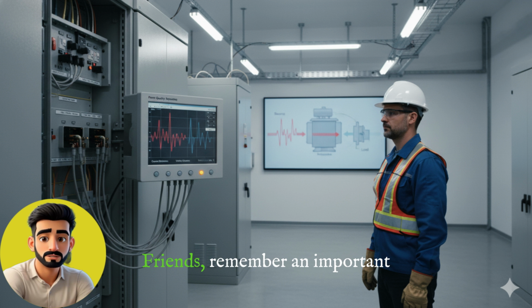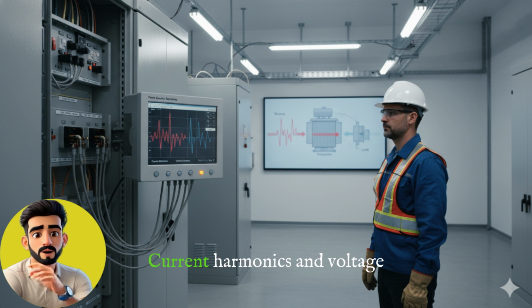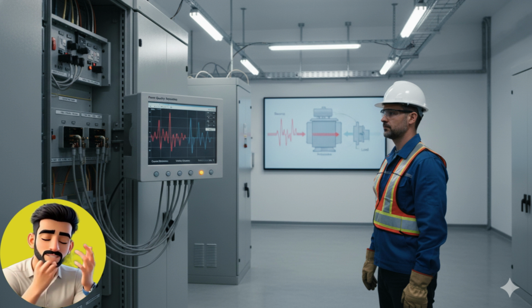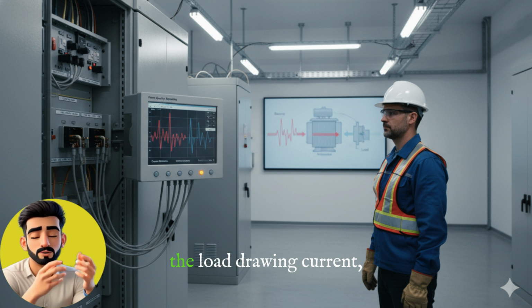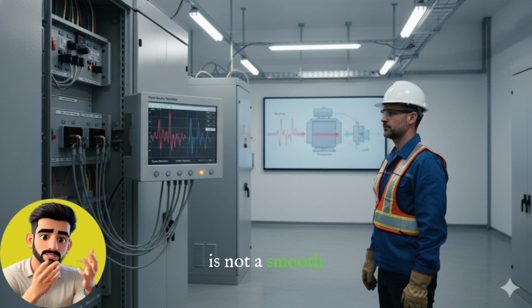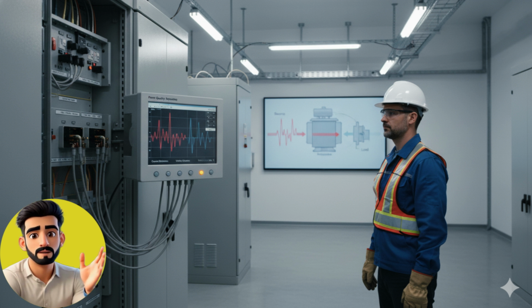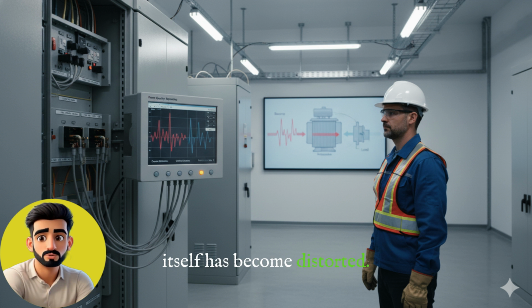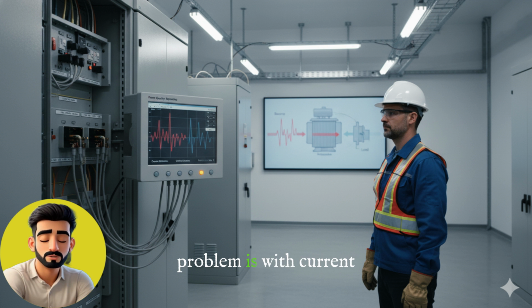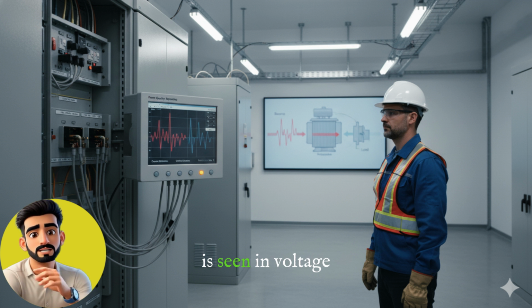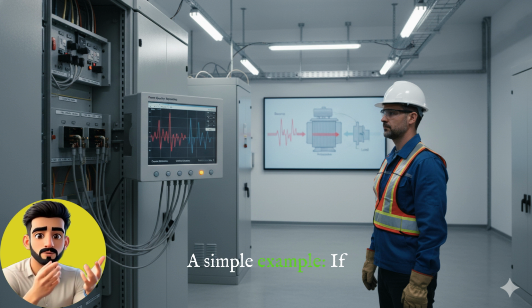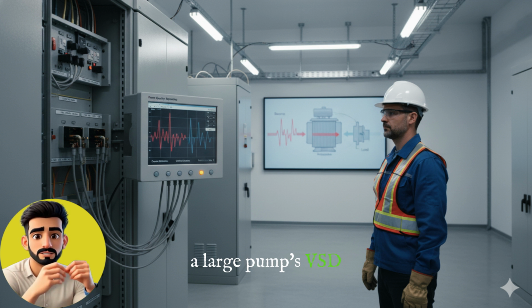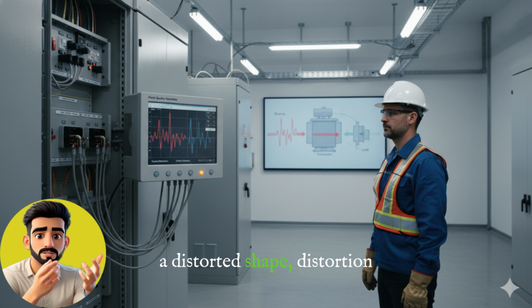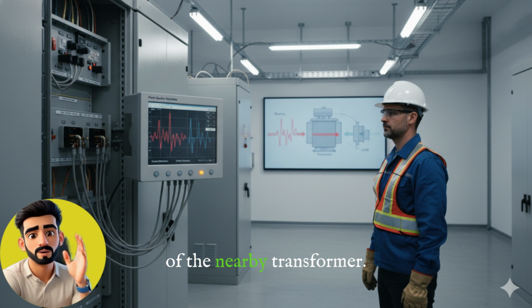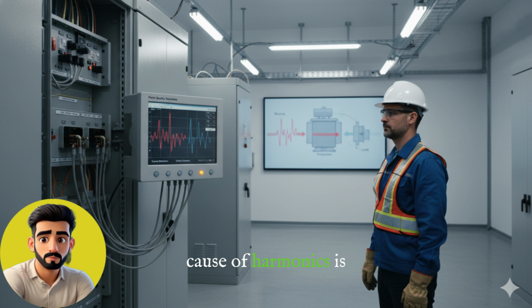Just that simple? Friends, remember an important point. Current harmonics and voltage harmonics are not the same thing. Current harmonics mean the load drawing current is not a smooth sine wave. Voltage harmonics mean the grid supply voltage itself has become distorted. Often in plants, the problem is with current harmonics, but the impact is seen in voltage harmonics. A simple example: if a large pump's VSD suddenly draws current in a distorted shape, distortion can also be seen in the secondary voltage of the nearby transformer. That's why the root cause of harmonics is the current, and the victim is mostly the voltage.